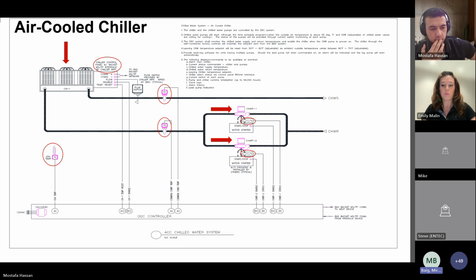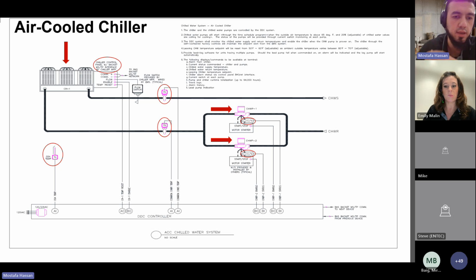What's the difference between the hardwiring and just using the inbuilt smarts of the pumps? VFD versus just getting what's shown here, enable and status, hardwiring it versus taking it to a communication via the VFD. So some pumps, like the Armstrong pumps, have the capability to just choose a mode of operation and run the pumps based on what's being selected rather than being hardwired. Would that be more useful than specifying pumps to be hardwired to the DDC here? It's shown here versus collecting that from the VFD.